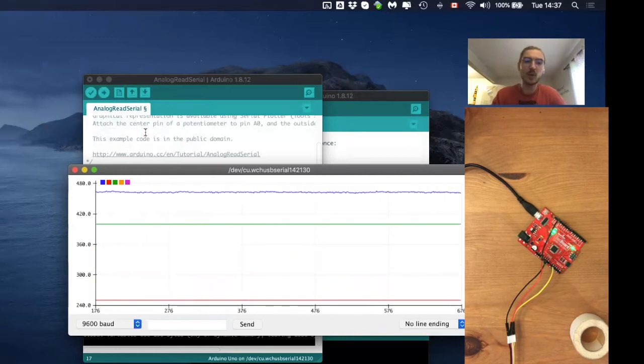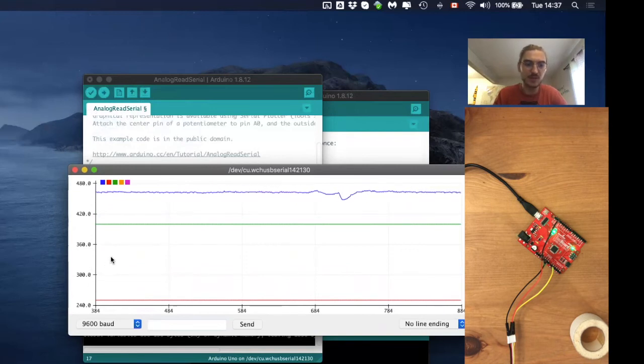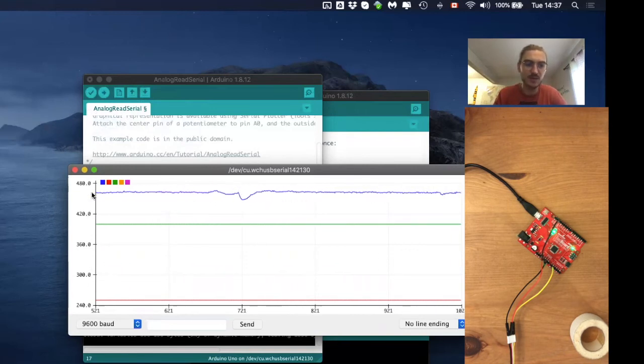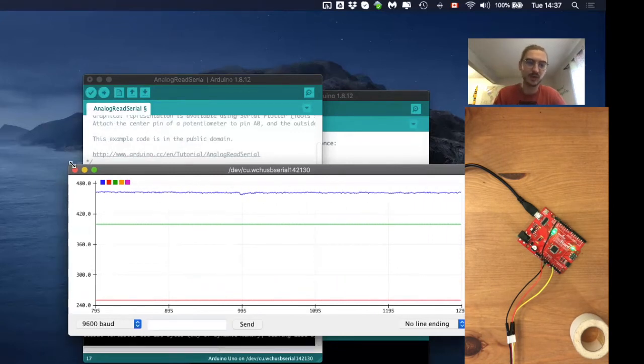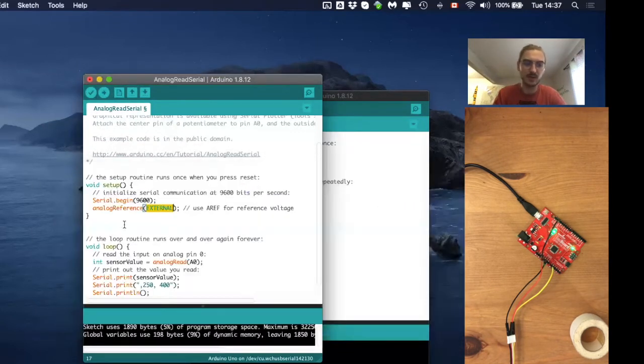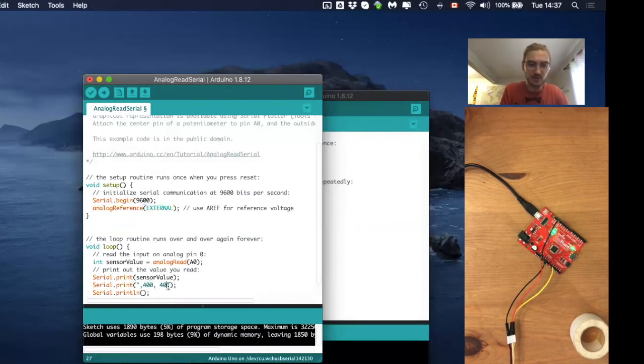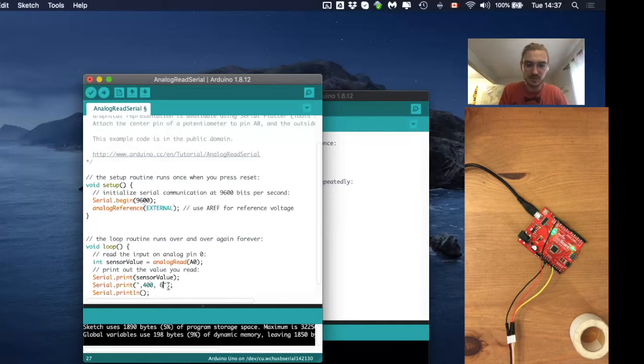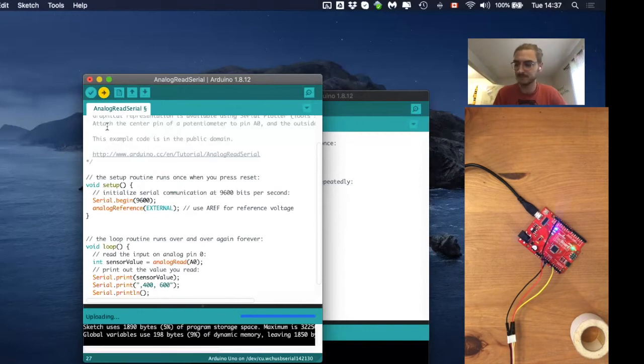We have to wait until the spike is gone. So now we can see that the default isn't like before somewhere around 300 anymore. It's now actually somewhere around 450. So we even have to change those two values here, the maximum and the minimum here.